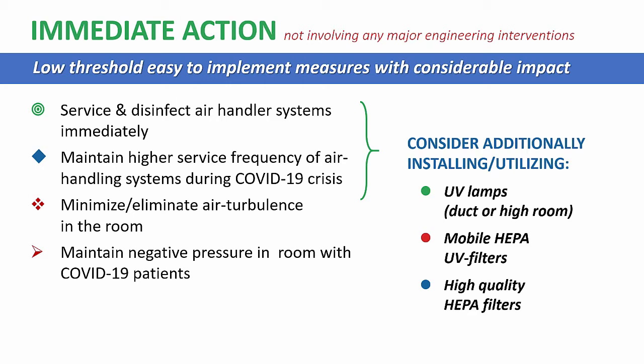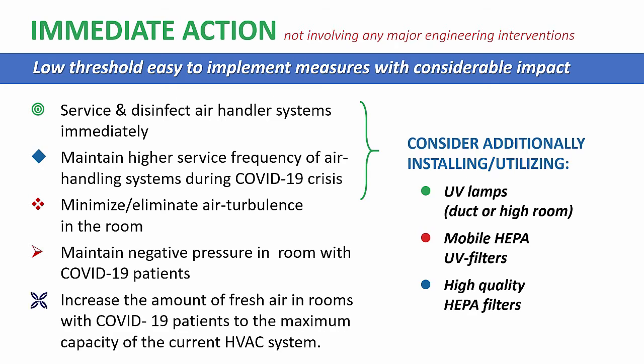There's another way to do it, a more professional way, that is with differential pressure sensors and controllers, and then you can control the air supply and exhaust to and from the room. This last one, increasing the fresh air amount to the room, for example a room with COVID-19 patient, is extremely important. What happens a lot of times is in air handlers, they close off or reduce the fresh air intake or the amount of fresh air coming in. This is to reduce energy costs, but that is dangerous, jeopardizing our health. And especially in this time with the COVID-19 pandemic, it's important to bring in as much fresh air as possible.